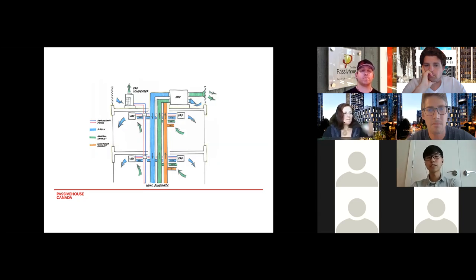The third point is that the garbage room is located in the basement of this building, within the treated floor area. We had to unbalance our ERV in order to put in a dedicated exhaust fan for that garbage room, because we wanted it to run independently and continuously relative to all the other systems. This way we ensured we mitigated the risk of odor transmission to other spaces.